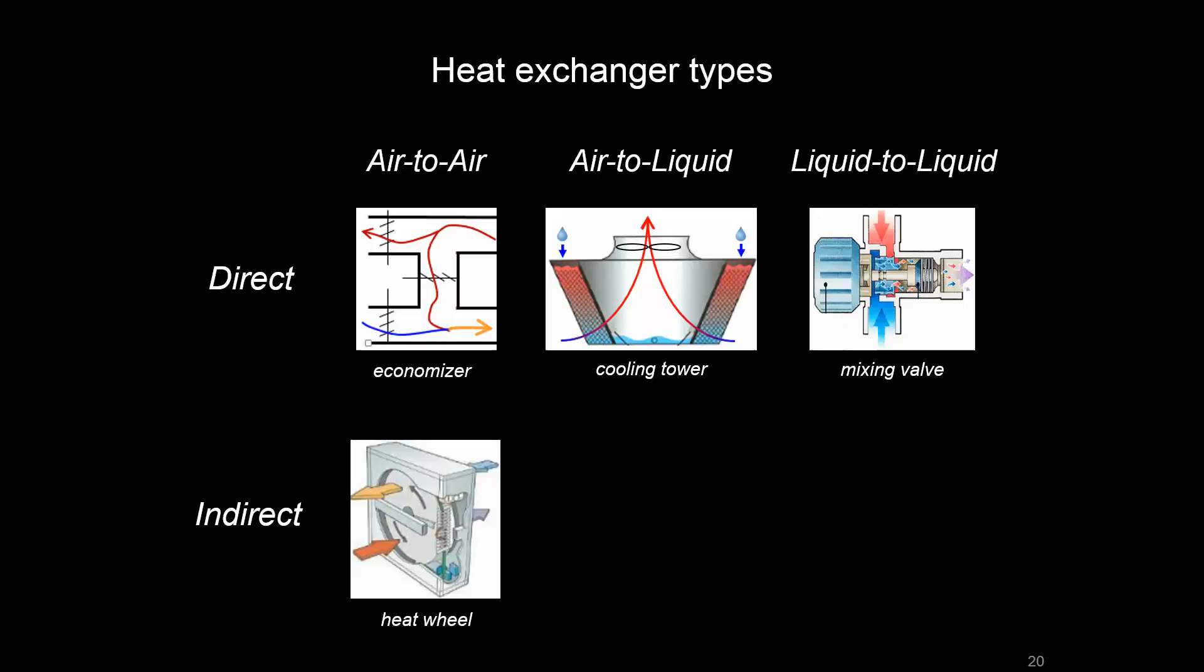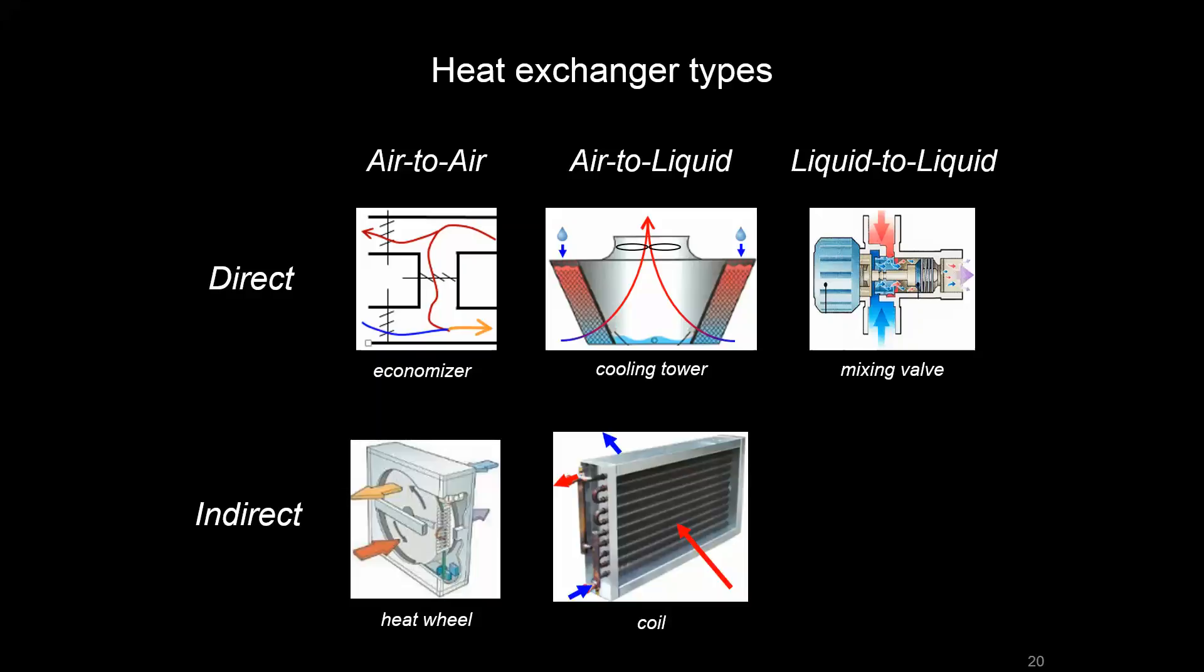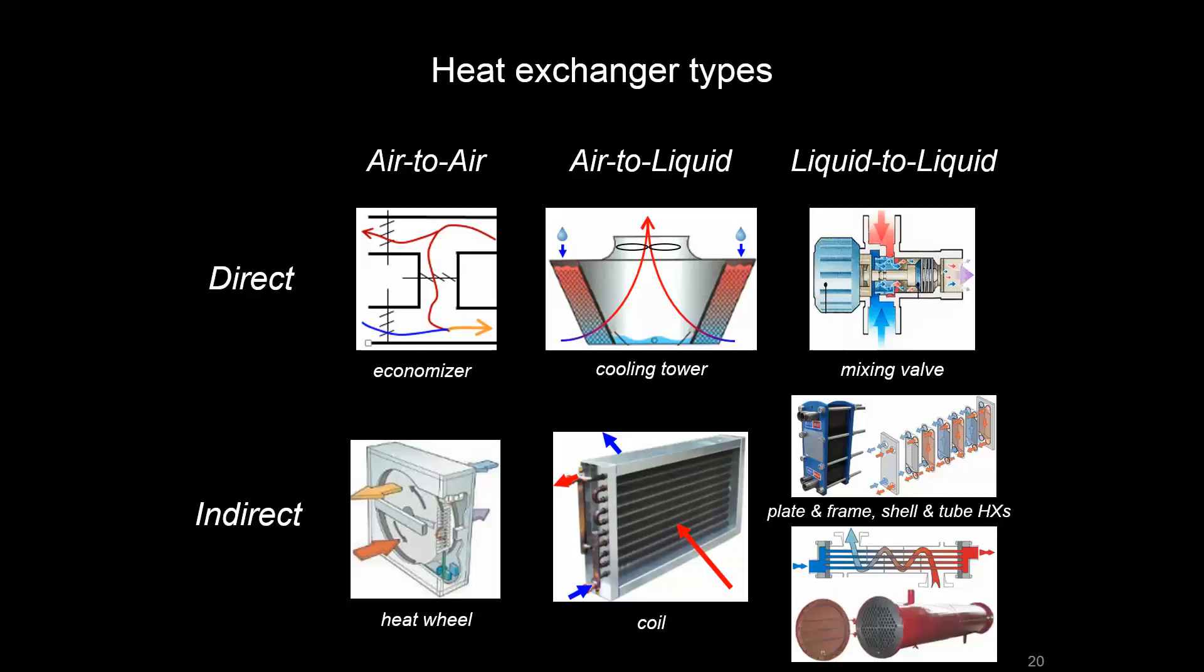And when we get into indirect heat exchangers, we can imagine a heat wheel that might be sitting at the inlet of an air handler, so that as you have exhaust air blowing across and outside air coming in from the other side, we have a heat exchanger between those two without any direct contact. Air-to-liquid would be something like a water coil or a DX coil. Liquid-to-liquid heat exchangers come in a variety of forms, such as plate-and-frame or shell-and-tube heat exchangers.